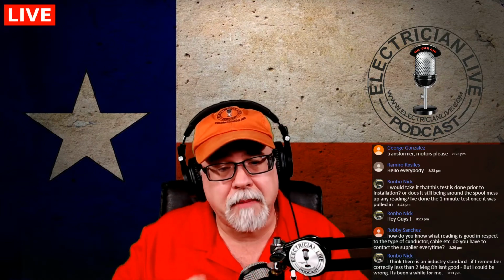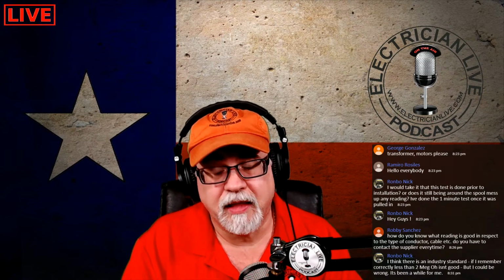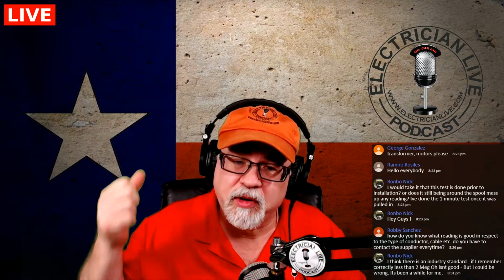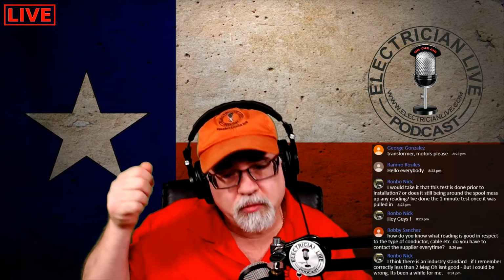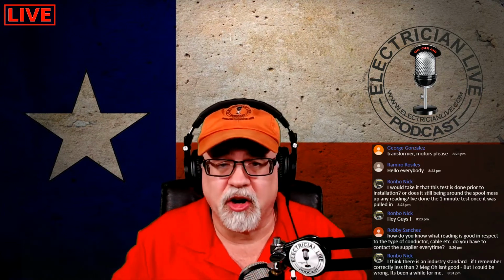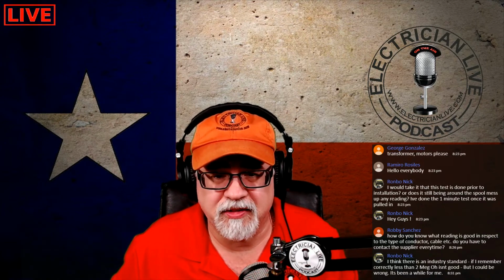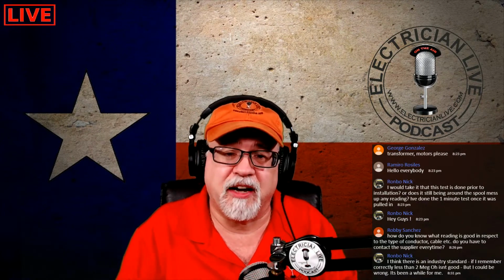The next thing that people ask me is they say, well, what about when I'm meg testing when I throw USE-2 conductors in a trench? And I go, how are you testing it? They go, well, we're testing a conductor, but then we stick a probe in the earth and we're doing a return through the earth. You can't do that, in the code, because the earth has too high of resistance. You're not going to get accurate readings through the earth if that's how you're trying to test it. It's not going to work.